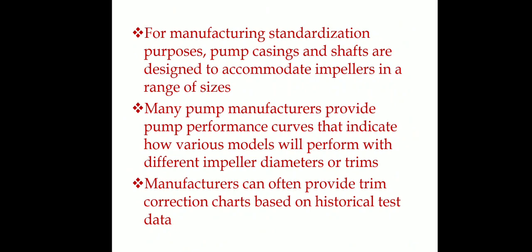Manufacturers also provide a trim correction chart based on historical test data. Using this previous data, we carry out the impeller trim correction. With proper impeller trimming, energy efficiency can be increased by about 20%.